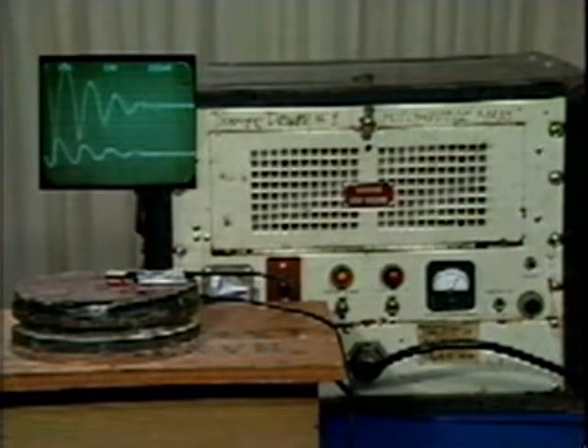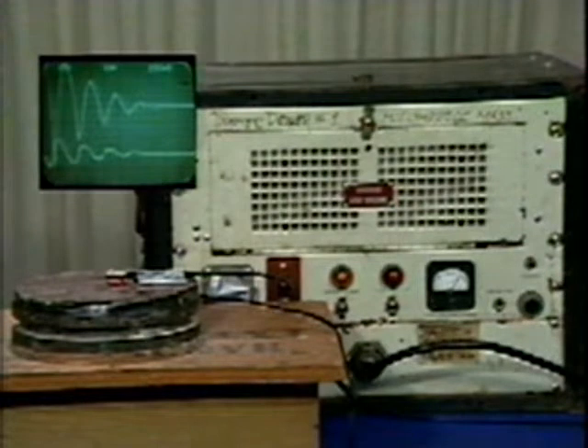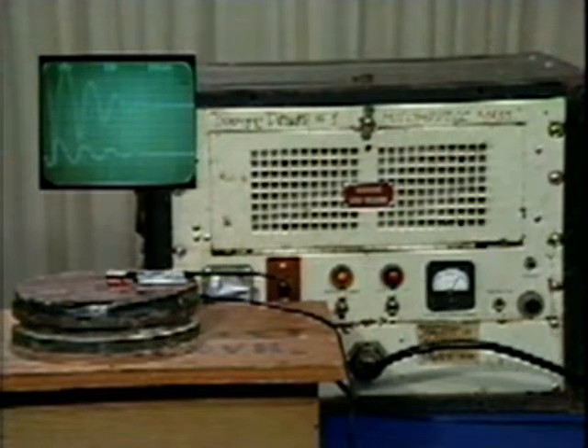The time axis is 0.2 milliseconds per division, so the period of the oscillation is about 0.3 milliseconds. The oscillation frequency is roughly the predicted 4 kilohertz. The duration of the lower trace current, and hence of the field, is on the order of 1 millisecond. The peak in the current on the lower trace is about 1 division. There are 1,000 amps per division, so the peak current is about 1,000 amps. This is in the range of the estimated value of 1600 amps. Remember, we've not accounted for losses in the spark gap and in the coil.